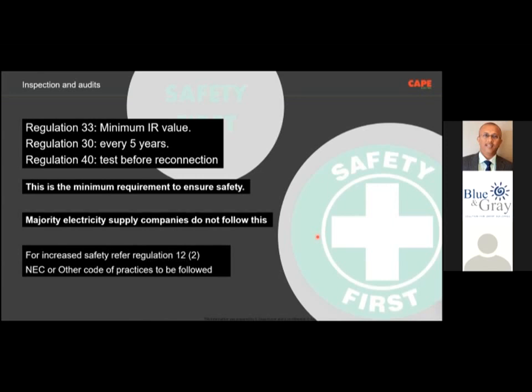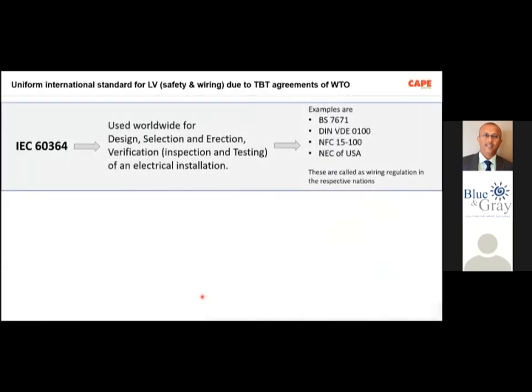Now, for anything more than this, the regulation says, 12.2 says, NEC or other codes of practice are to be followed. So basically, once we start from our rule by the Government of India, the safety regulation says you should do the insulation resistance measuring, for example. The simple name is megger. So you should do the IR test, and more than that, you should do as per what is written in the NEC and other codes of practice. I showed you in the previous slide, IS 732/1989 has included 10 different tests, and we don't do them now. So if you have not carried out this particular testing, you cannot call your electrical installation safe.